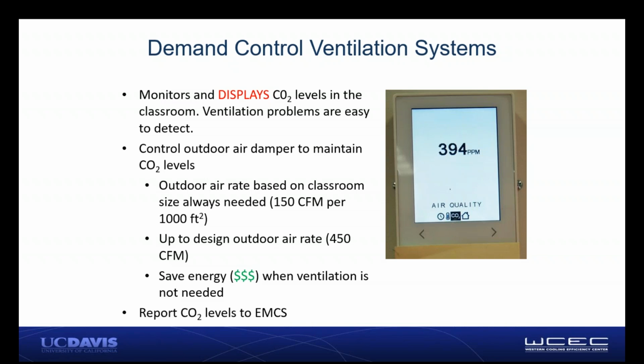Here is a display in one of the classrooms that shows—you can click the little temperature button or the CO2 button, and then the CO2 is displayed to the teacher if they want to know, and that signal is also sent back to the EMCS system. This is really obvious; it tells you right away if you have a ventilation problem. So if the contractor and the commissioning agent didn't get it installed properly and didn't commission it properly, you know right away. CO2 sensing isn't particularly expensive, so I think this is a very worthwhile investment.